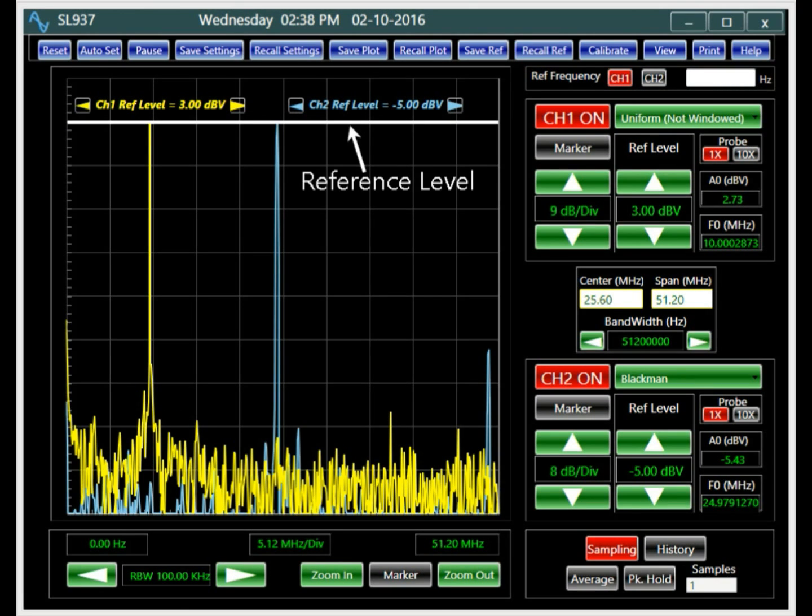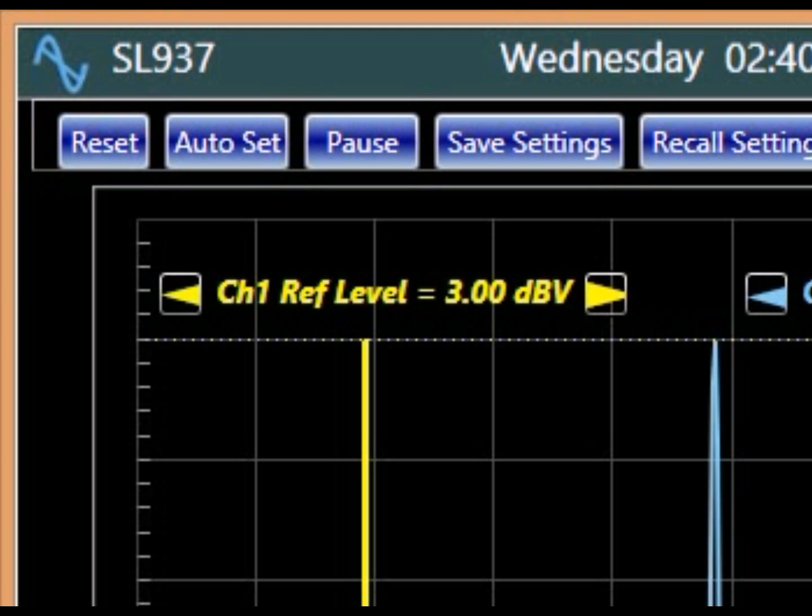The reference level is another important parameter of a spectrum plot. The spectrum analyzer signal measurements are referenced to a horizontal level at the top of the screen referred to as the reference level. The frequency components of a signal are measured to this reference. A 3 dBV reference level means that the full scale of the spectrum analyzer is set at 1.4 volts RMS or about 4 volts peak to peak.